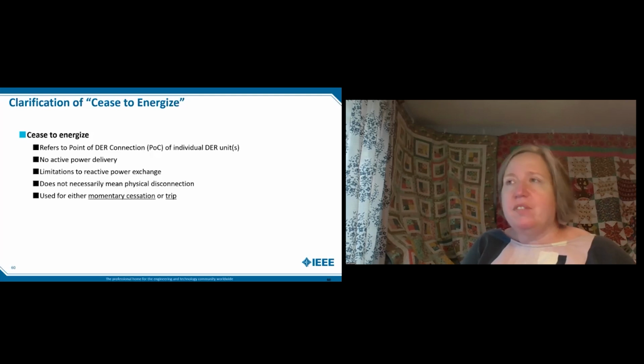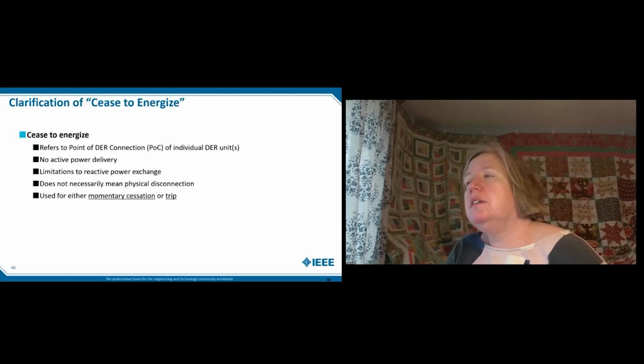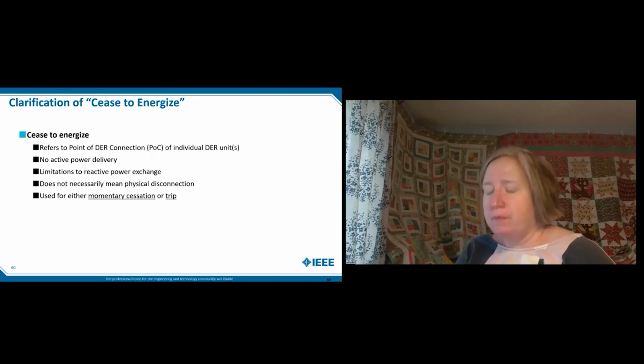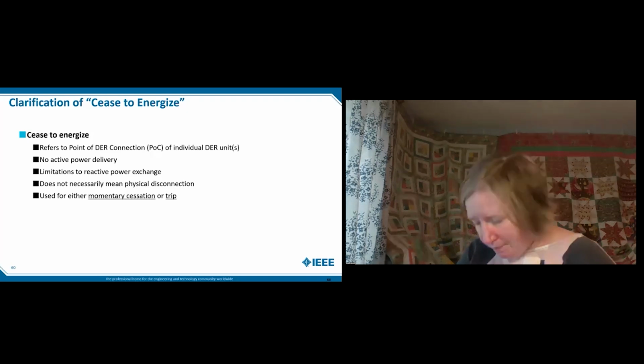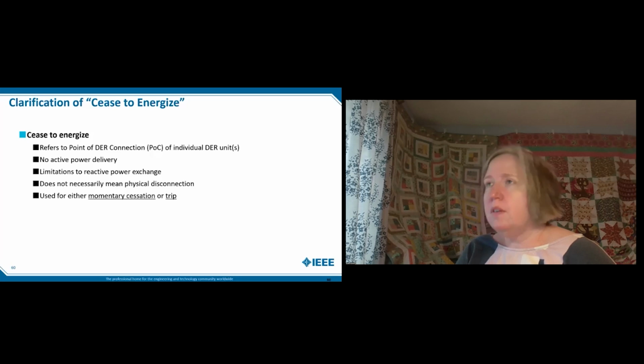I'm also curious how your utility deals with the return to service. The original 2003 version by default had a 5 minute delay. So if a DER asset trips, and here's the key thing, it must monitor voltage and frequency for 5 minutes before it can be reconnected. Now, in a small system, depending on DER, like in Alaska, 5 minutes is a long time. I'm interested in your operational experience. Are you allowing accelerated return to service? Are you seeing cease to energize actually as a useful tool as penetration comes up in your own system?